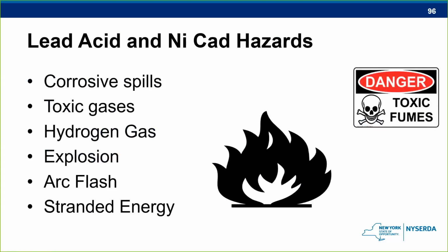Okay, first we're going to talk about there were a couple of different chemistries. The first chemistry that we'd like to talk about is this lead acid chemistry or the nickel cad. They're kind of similar, but they're known to have their corrosive spills, and we usually see them in the UPS sector, as I mentioned before, in hospitals or in very critical areas where they need that backup energy. So these things are not new to us. They're probably already in your location all over the place, these lead acid batteries. And we've seen some spills, but with lead acid, that's our biggest concern, is these spills.